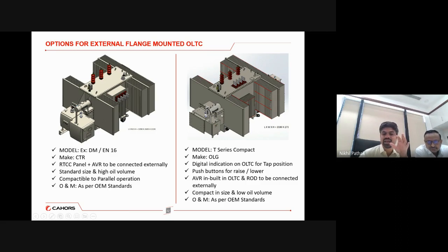Secondly, this has an inbuilt AVR, so an external remote operating device or the RTCC panel is not compulsory. If we give the auxiliary supply to this AVR from the transformer panel, LT panel or something outside, then without even connecting the RTCC panel or ROD panel, the OLTC automatic operations can start. Only if we want remote operations is this ROD required. So this is the difference. And this ROD you can install in your indoor panel room also, as well as an external one. So these are the two differences.